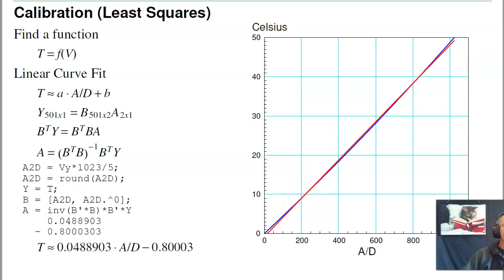If I plot the residual, that's the difference between the actual temperature and my curve fit. That's my basis times my constants. I see this shape. The stair steps are the A to D reading. The A to D is stuck at integer values. And so you're seeing a little bit of change right here. The other shape, the parabola, that's due to the calibration error. That says if I use a linear curve fit, I can't compensate for that parabola. But what I could do is use a more complicated curve fit, such as a parabolic curve fit.